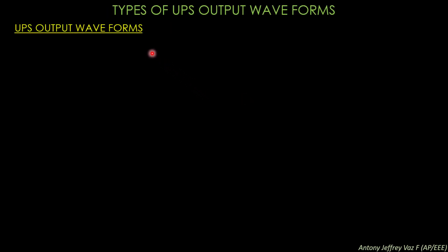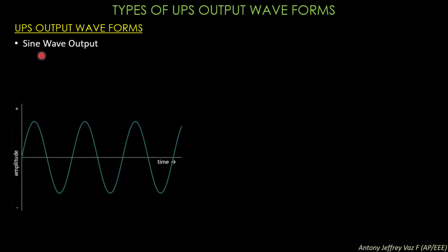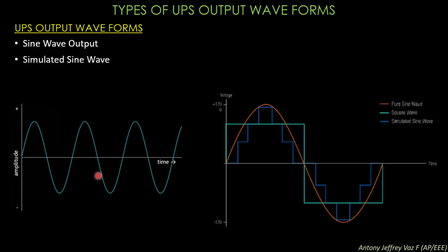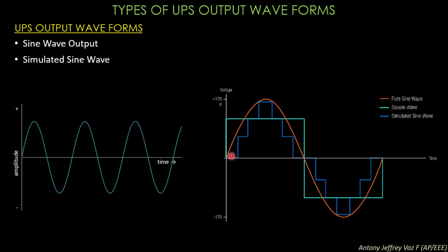Next we will look at UPS output waveforms. The basic output is a sine wave at power frequency. The other type is the simulated sine wave output — shown here as a blue line — which most older UPS produce. Modern UPS produce a perfect sine wave. The simulated sine wave produces harmonics, causing humming in fans and tube lights connected to older inverters, whereas modern sine wave inverters produce no such noise.